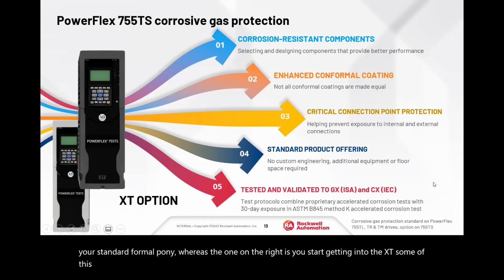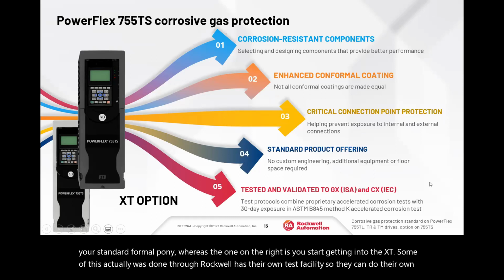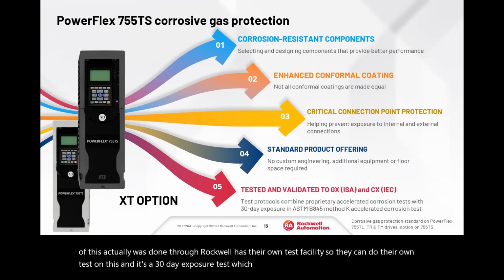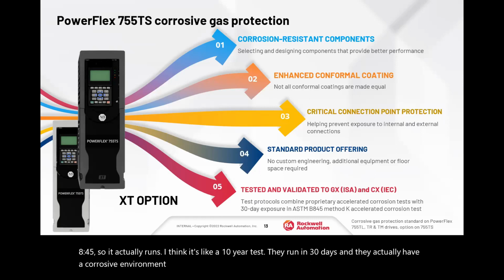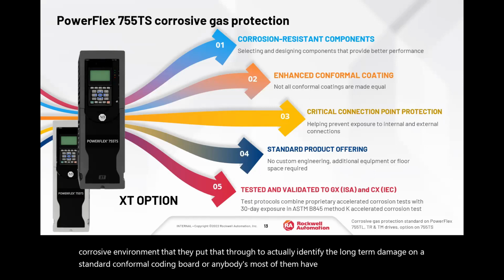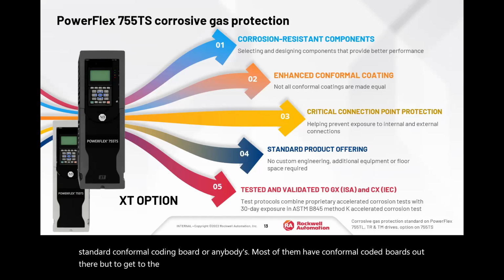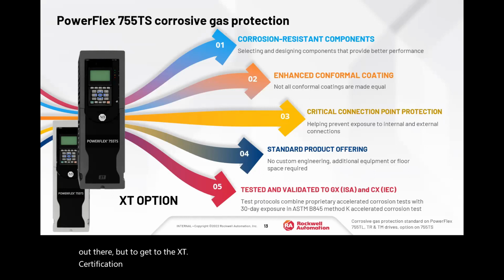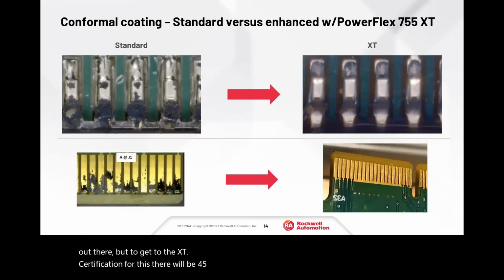Some of this was done through Rockwell, which has their own test facility, so they do their own tests on this. It's a 30-day exposure test, to the ASTM B845. I think it's like a 10-year test they run in 30 days, and they have a corrosive environment that they put that through to identify the long-term damage on a standard conformal coated board, since most have conformal coated boards out there, but to get to the XT certification for this. This is just an example.